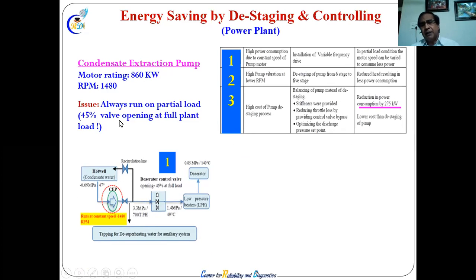Can you start a machine like this? That means there is an engineering issue. I'm not saying it in a wrong way to say somebody is not capable, but we should think that we want 50% partial load, but you want a pump like this, which means the total decision was wrong. But once the machine has come, what can be done? The promoter has to run the factory, right? So they initially put a VFD.